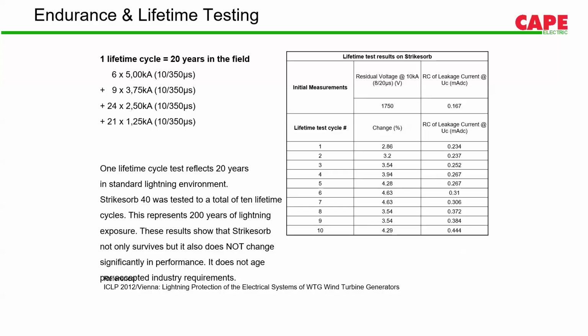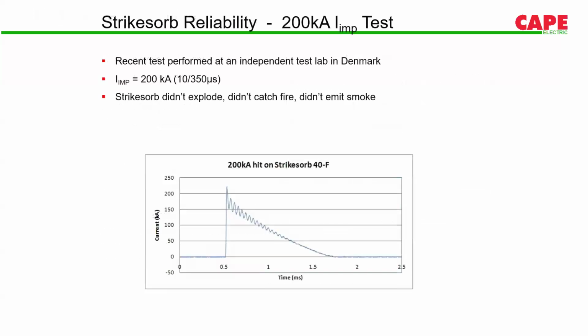That means a Strikesorb 40 in a general lightning environment like India can have a life of around 200 years. Of course nobody is going to wait for 200 years, and the panel in which the SPD is installed will not work for 200 years. But without any doubt, the SPD will be there for at least 30-35 years, which is the life of the panel. A Strikesorb 40 series SPD, which has an impulse current rating of 12.5 kA, has been tested with an impulse current of 200 kA, which is quite high. Practically it is almost impossible for an SPD to have this high rating of impulse current.